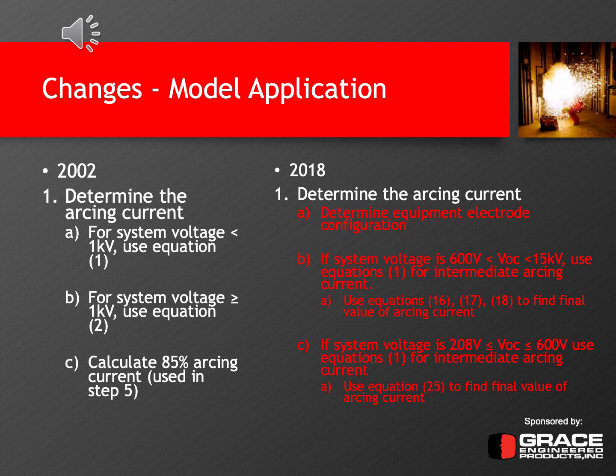In 2018, you still need to determine the arcing current, but there's a number of things you have to do before that. First off, you need to determine the equipment electrode configuration. So that's your HCB, your HOA, VCB, VCCB, and VOA electrode configurations. And then you need to look to see if the system voltage is between 600 volts and 15 kV, and if so, use equation 1 for the intermediate arcing current. You then need to use equations 16, 17, and 18 to find the final value of arcing current, which takes into account some of the correction factors.